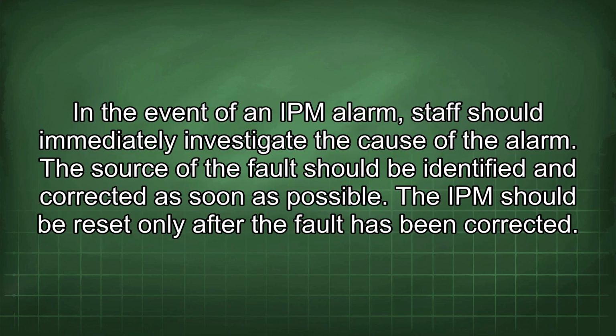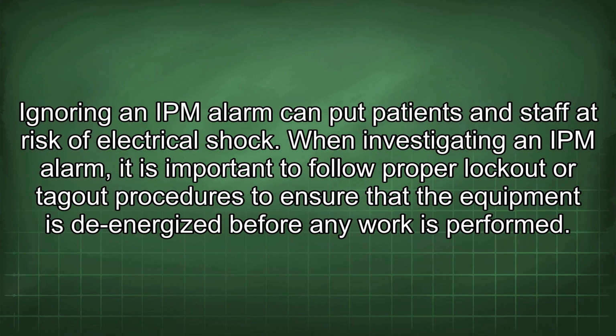In the event of an IPM alarm, staff should immediately investigate the cause of the alarm. The source of the fault should be identified and corrected as soon as possible. The IPM should be reset only after the fault has been corrected. Ignoring an IPM alarm can put patients and staff at risk of electrical shock.